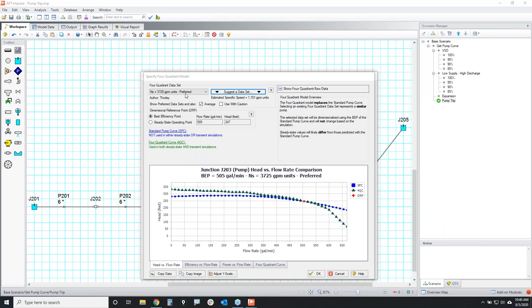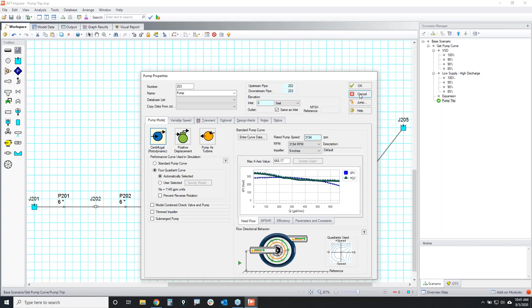Where does that information come from? Well, it comes from your flow rate value, your pump head, and your rated speed at the best efficiency point. And so as you can see here, at the BEP value, those two curves, the 4-quadrant curve and your standard pump curve, match pretty well. But here's the issue: once your system flow starts to get lower or higher, the curves deviate from each other. So the more deviation that you have, the less accurate your results are going to be. Now, these are all approximations themselves. And so, again, the best way to do it is to just use the one that we've provided for you, and you can see that the curves will match a lot closer.